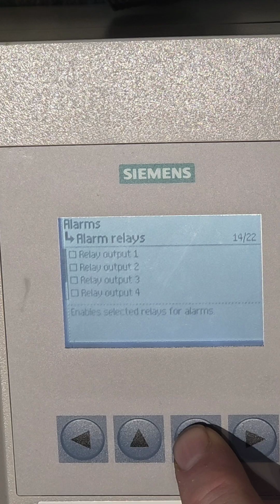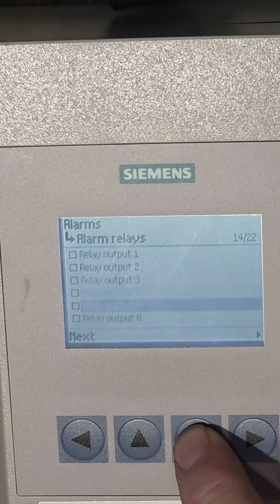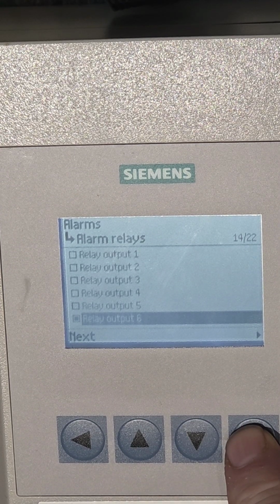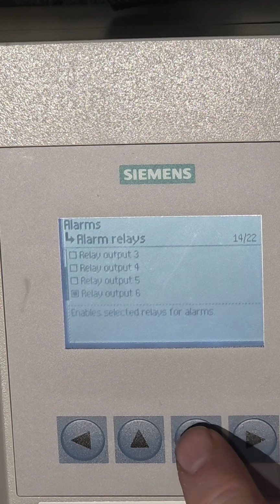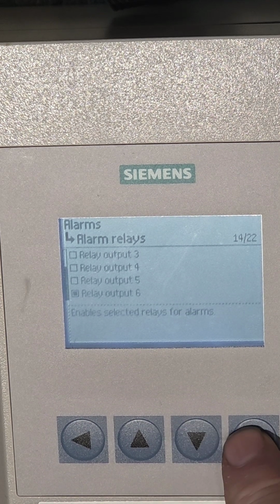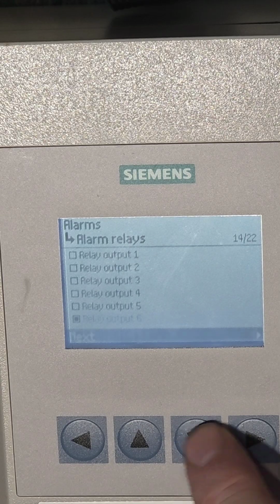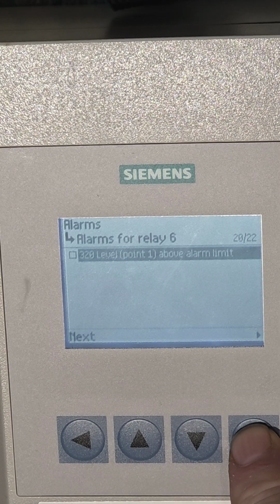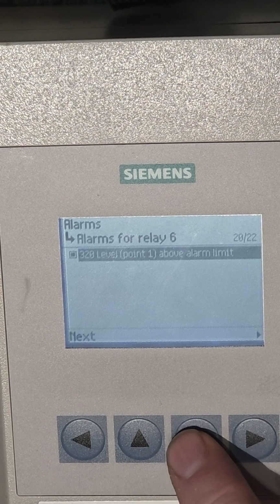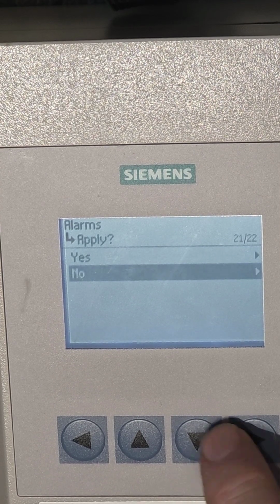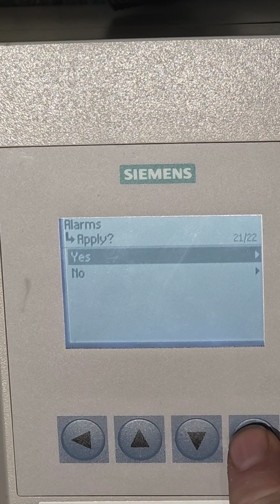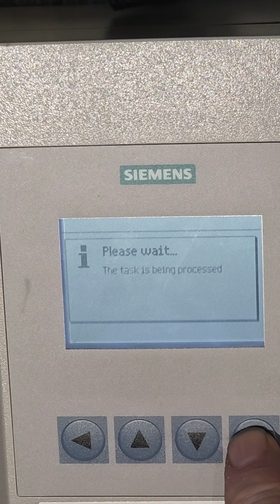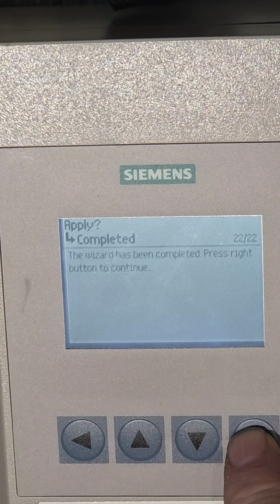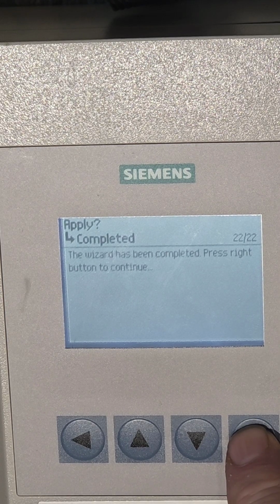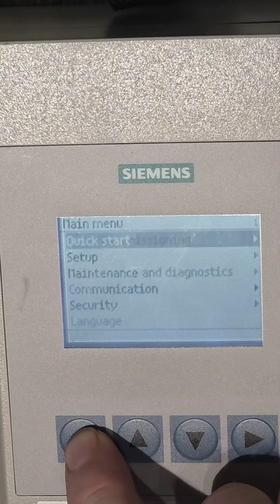So I want that to be relay 6 for the high level alarm. Down to next, and I'm going to choose above the alarm limit again, so highlight that, down to next, right key, apply the changes, yes. And just come right back out of that.